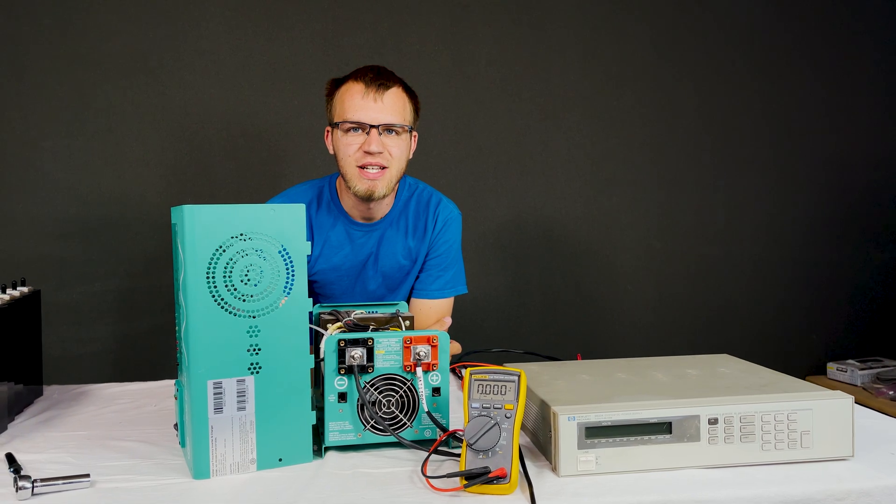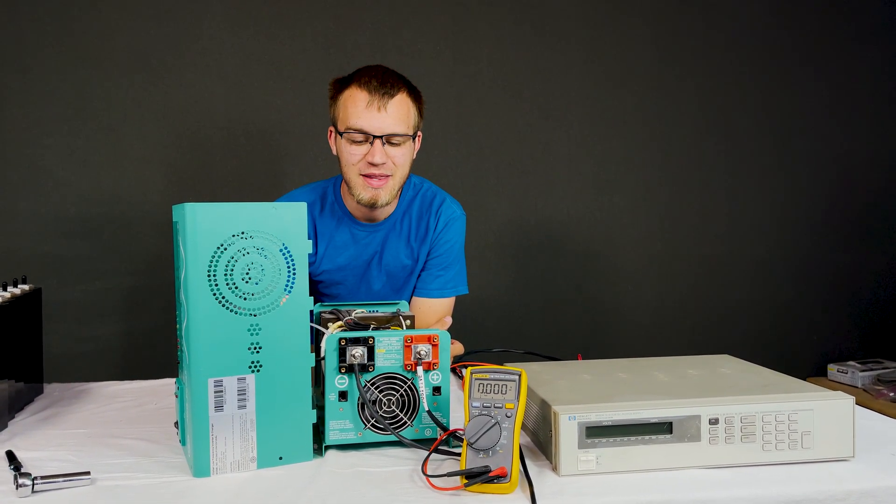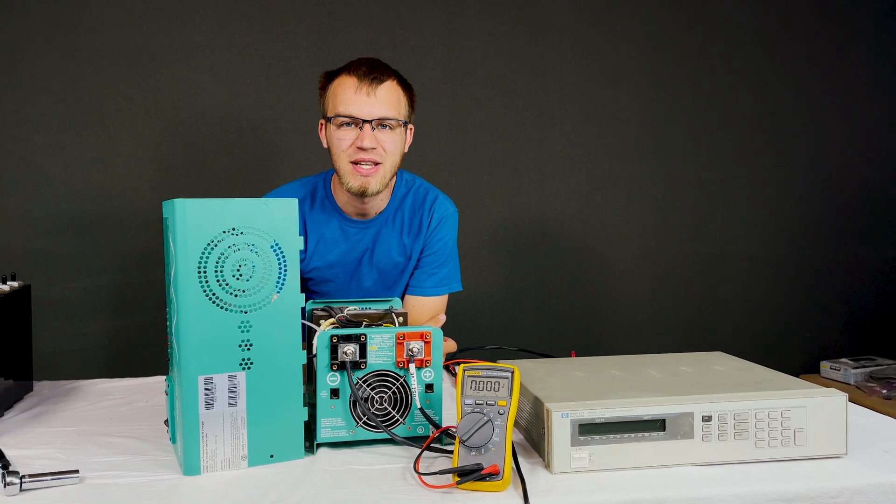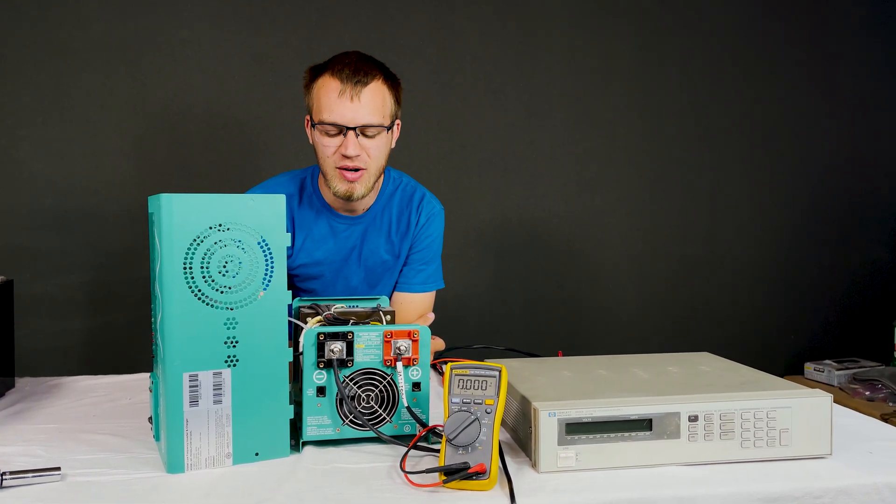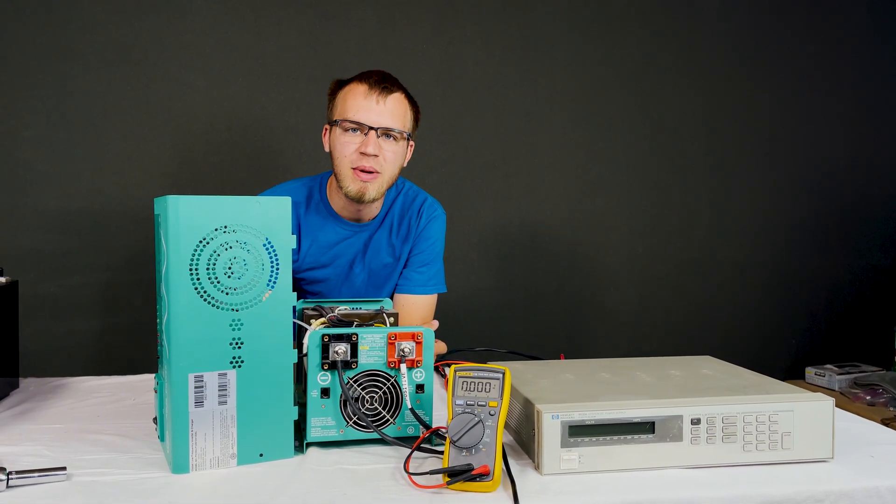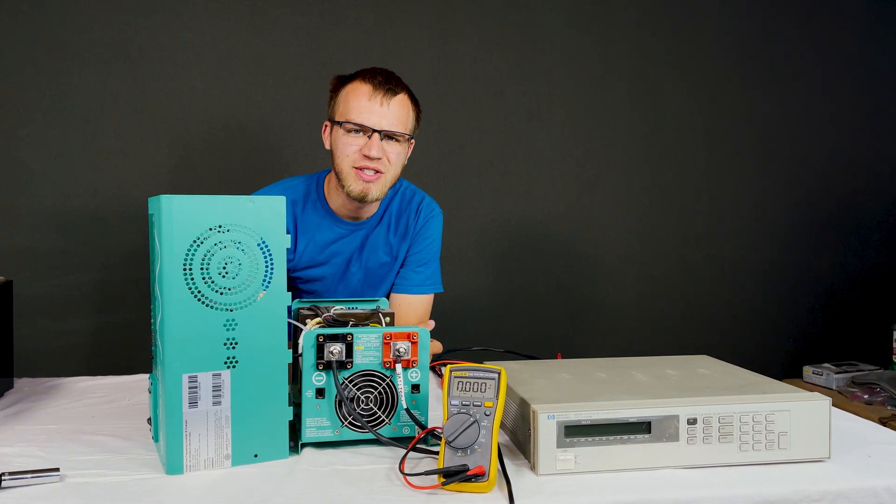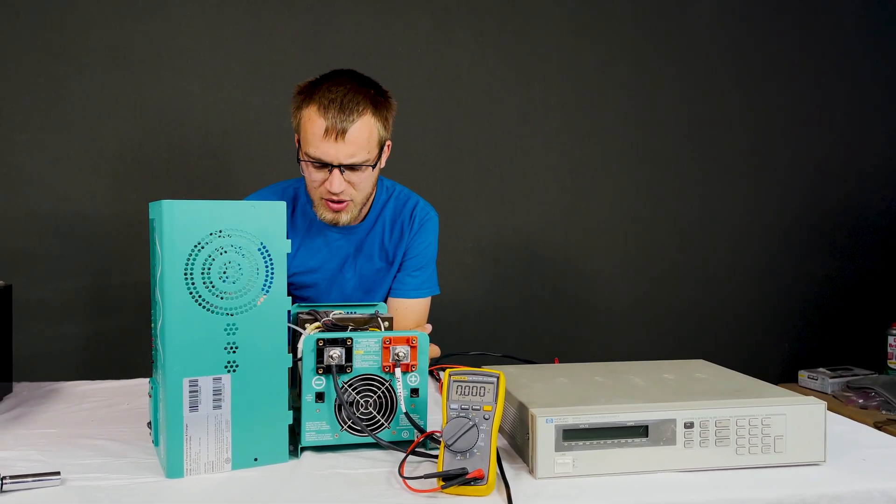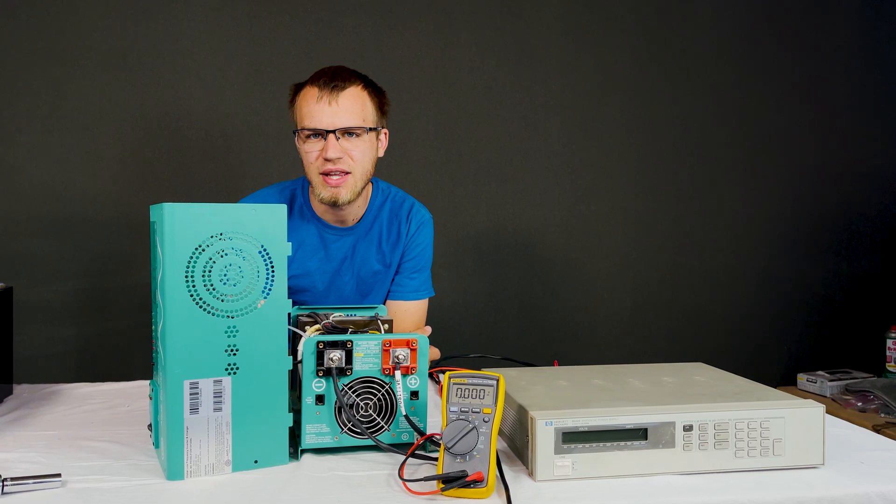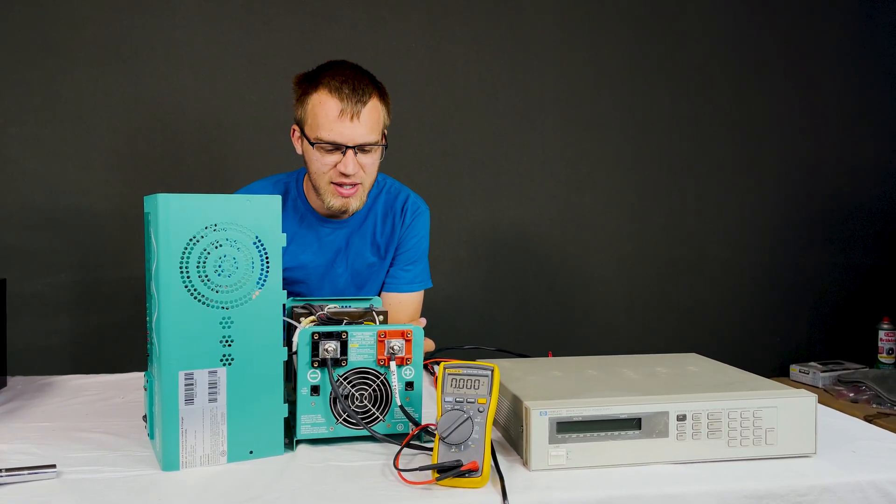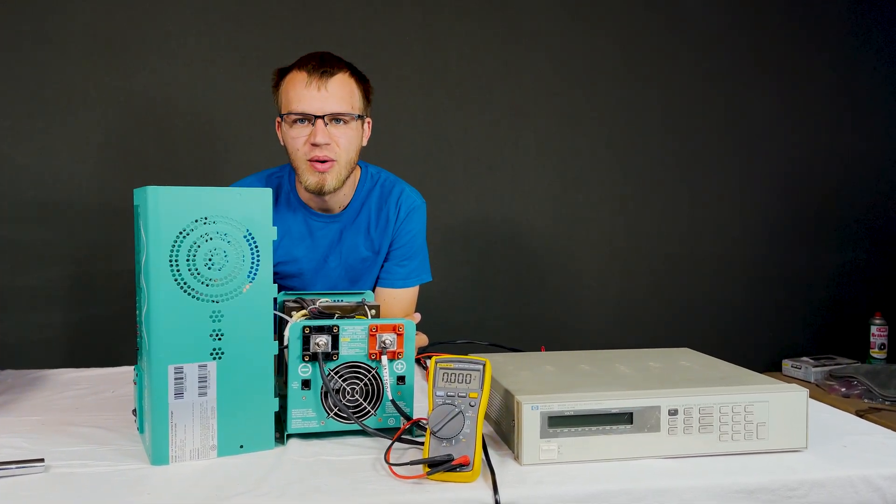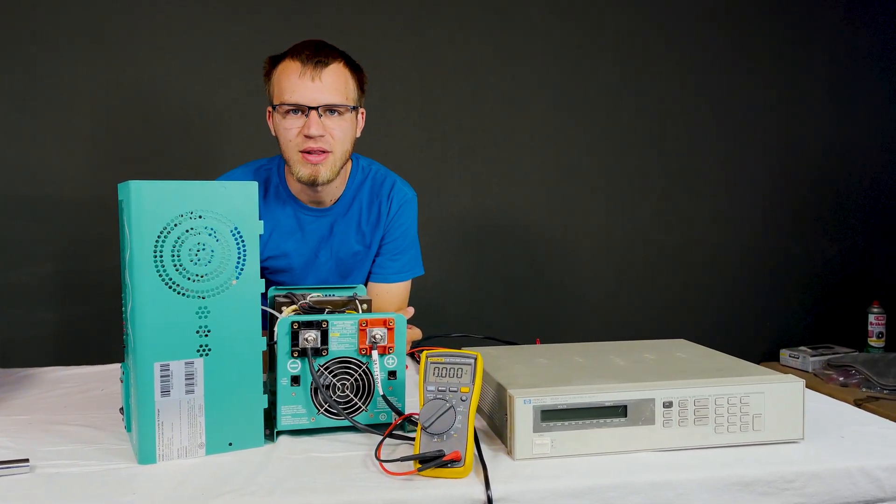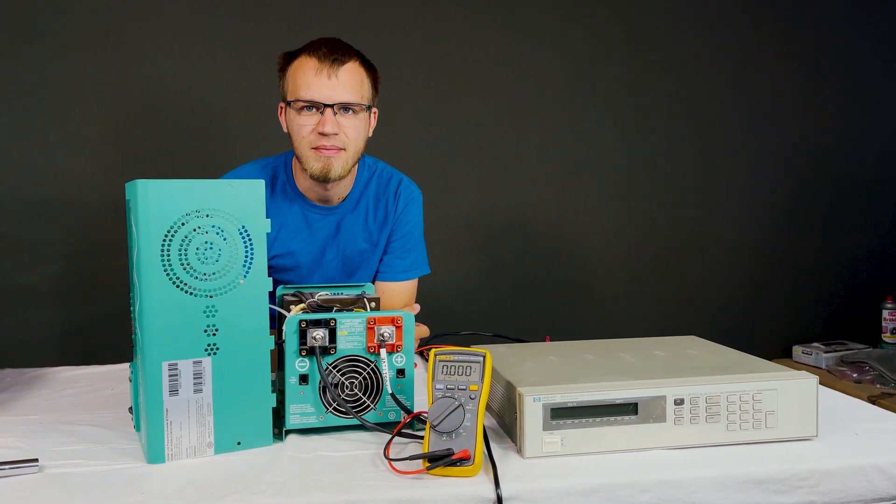So it's not typically like me to go for a warranty replacement but this guy's covered under warranty, at least I believe it still is. So I'm going to stop digging into it about here. It's nothing obvious, it's not obviously blown up, it just stopped working and for some reason blew that 300 amp fuse. Usually when you run currents like that, like 300 amps, you're bound to find something that's blown up, but nothing I can see here. So we're going to contact AIMS Power, they're the OEM of this product, and see what they say.